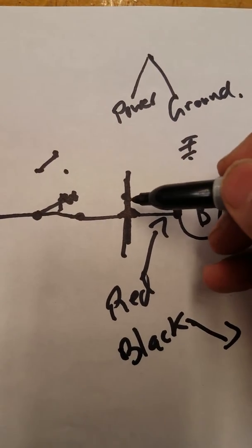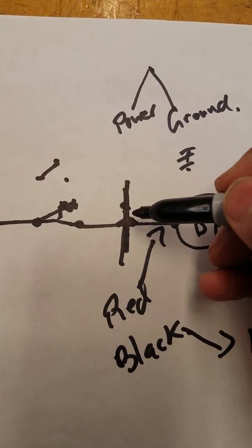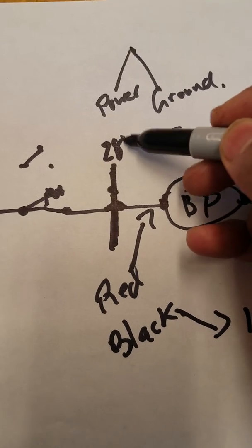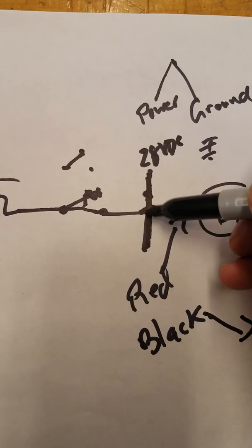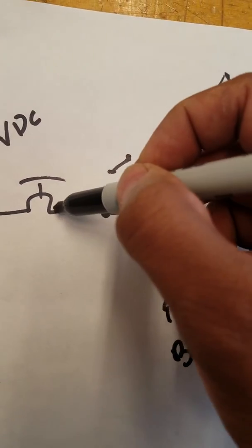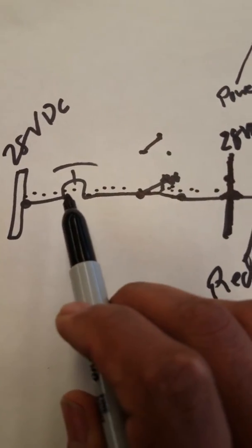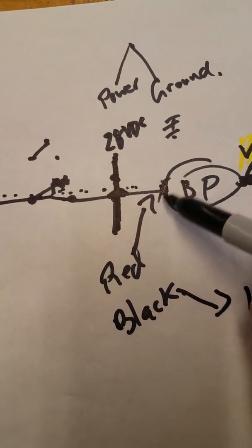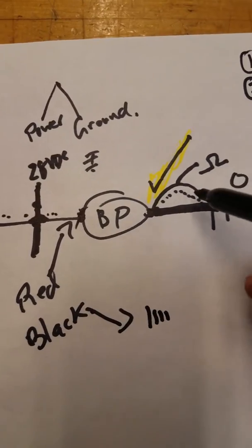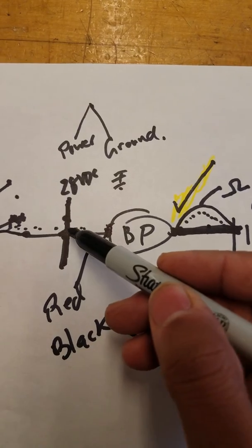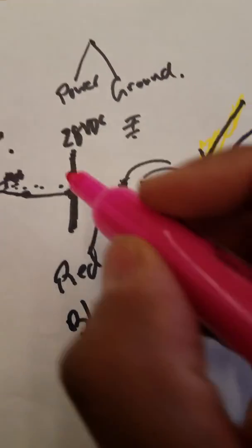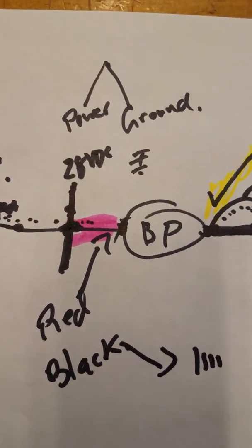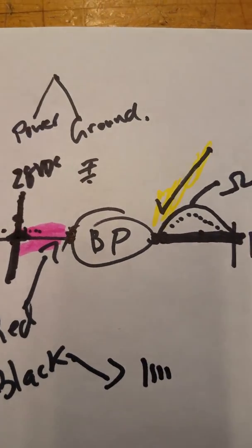If you read 28 volts DC at the terminal strip, that tells you the electrons came from the bus, through the circuit breaker, through the switch, and are waiting at that terminal strip. But somehow they didn't make it to the boost pump. That gives you a clear hint — process of elimination. You had ground, you checked power, no power at the boost pump but power at the terminal strip. So the problem is in the wire between the terminal strip and the boost pump.